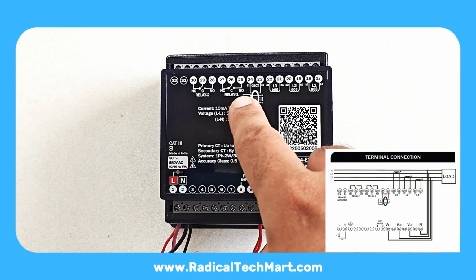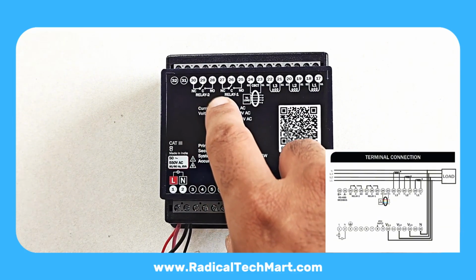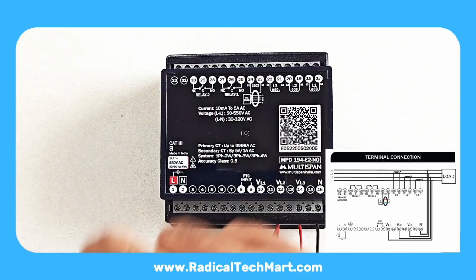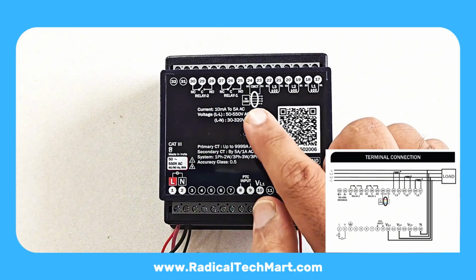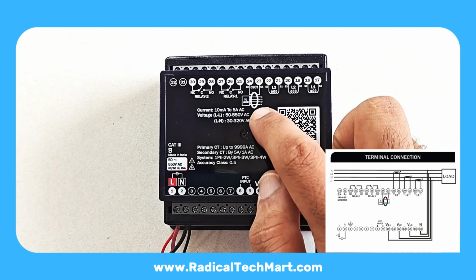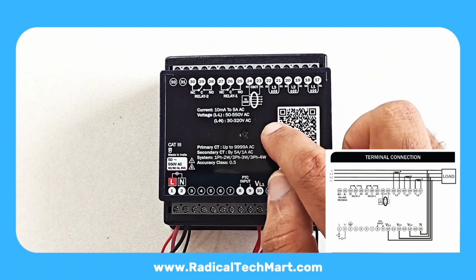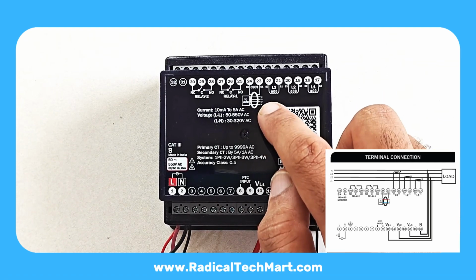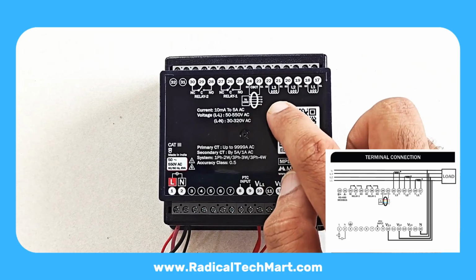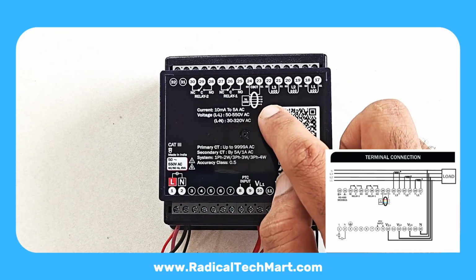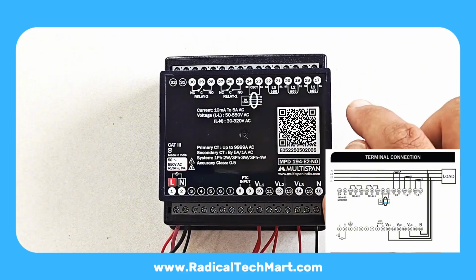Terminals 10, 12, and 14 voltage inputs, R, Y, and B phases. In this demo, we only have a single phase available, so we have looped the same phase to R, Y, and B. Terminal 16, neutral. Neutral is looped from terminal 2 to terminal 16.